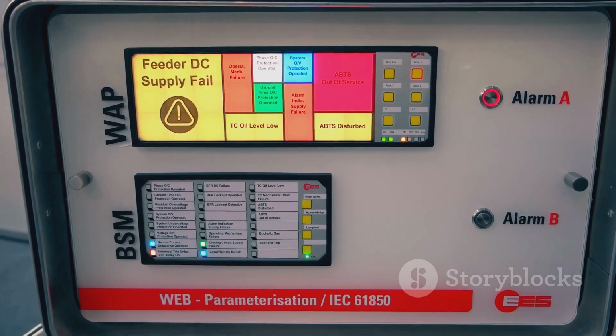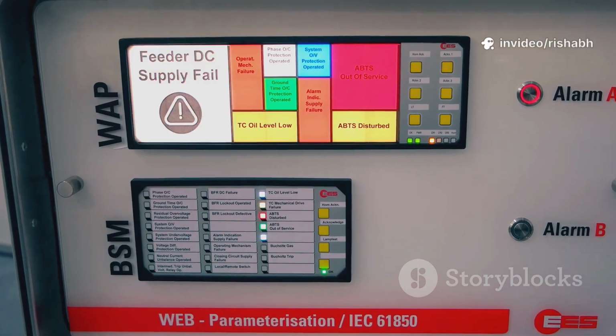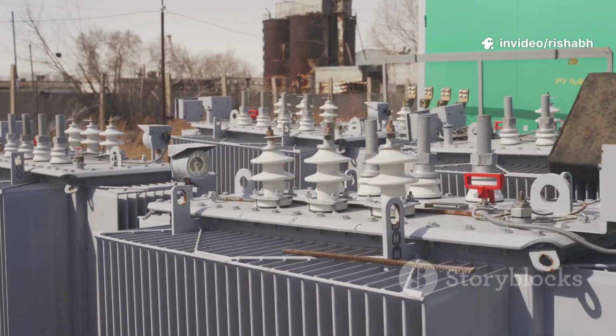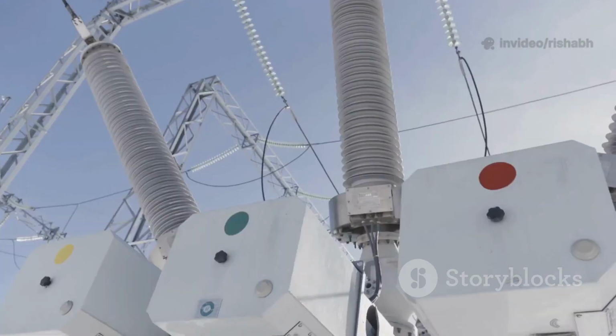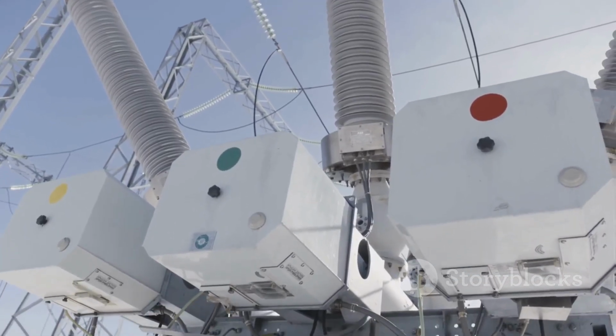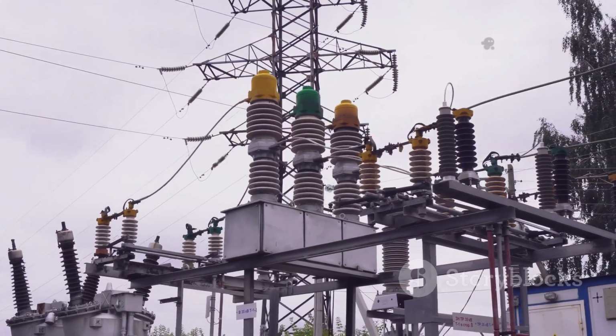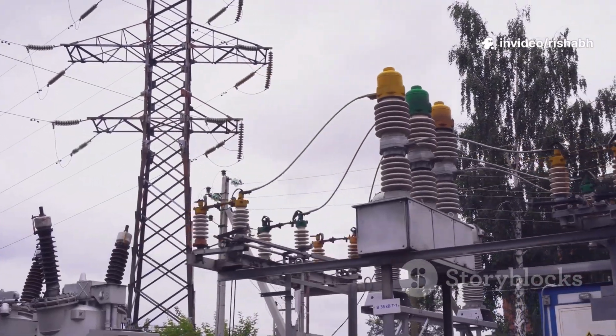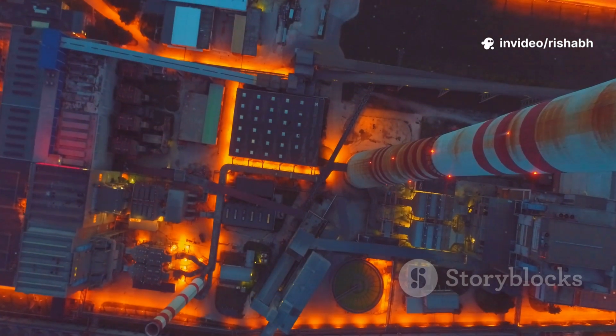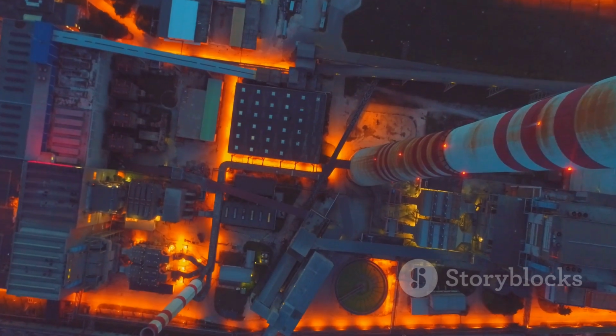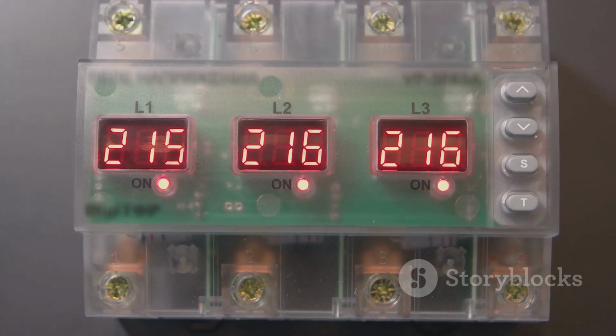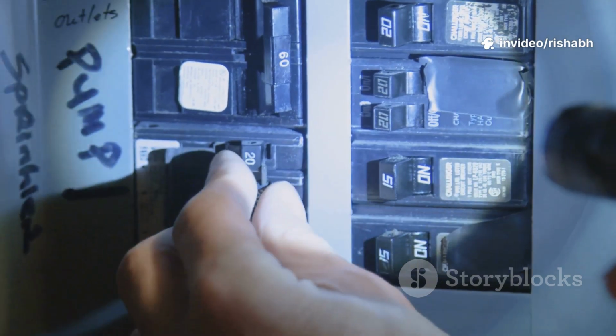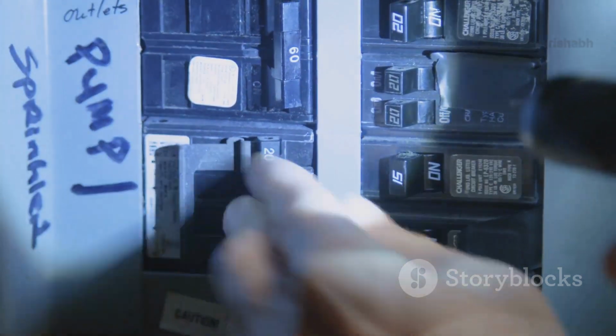Finally, the 845 provides protection against what we call over-excitation. A transformer is designed to operate at a specific voltage and frequency. If the voltage gets too high or the frequency drops too low, the magnetic core of the transformer can become oversaturated or overexcited. This condition generates extreme heat very quickly and can cause rapid damage to the transformer's core. The Multilin 845 monitors the voltage-to-frequency ratio, volts per hertz. If this ratio exceeds a safe threshold, the relay identifies the dangerous over-excitation condition and takes protective action to save the transformer from a very expensive failure.